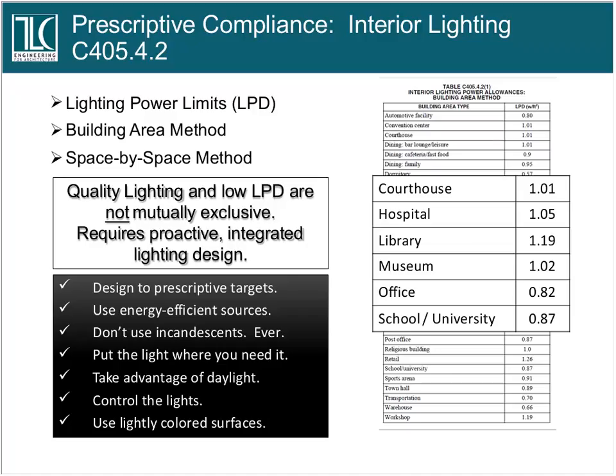And I did a project for the Air Force on the Redneck Riviera down in the Florida Panhandle. It was a fitness center, and we had really low lighting power densities in the cardiovascular room. So we had these fixtures that hung down below the ceiling that shone light up onto the underneath side of the roof deck, and we painted it white, and the corrugated metal roof deck painted white, all of the ductwork and all of the stuff that was going to be above the lighting fixtures, we wanted to paint white so it would reflect that light down into the space and be a relatively shadow-free lighting solution.